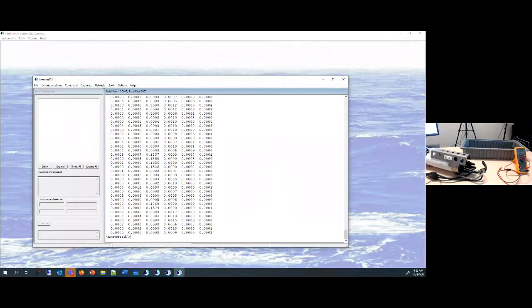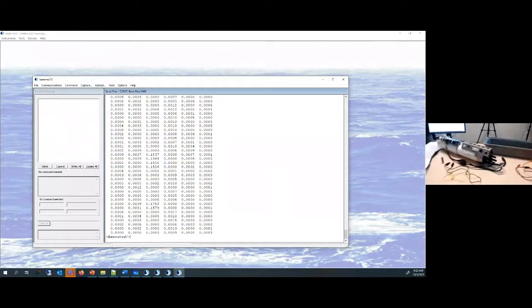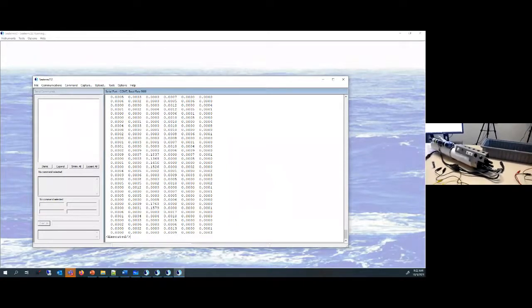But essentially, the step is to simulate an auxiliary voltage sensor sending data to the CTD by using a battery that's outputting 1.5 volts. Since we know it's 1.5 volts, if we see 1.5 here, then we know it's getting data from the sensor, or it should be. At that point, we can troubleshoot the sensor itself.